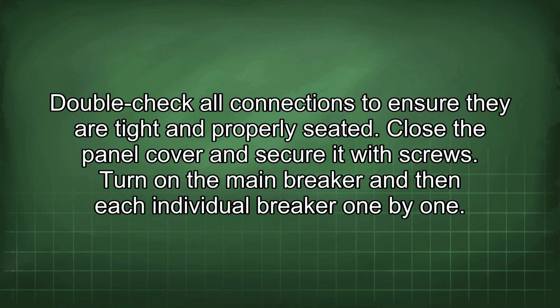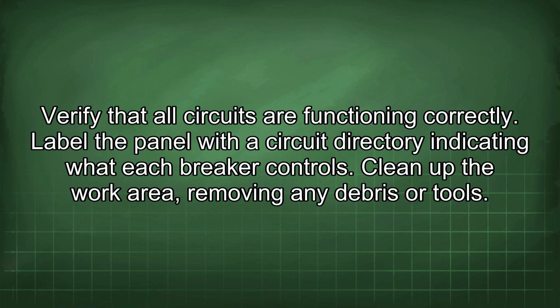Close the panel cover and secure it with screws. Turn on the main breaker and then each individual breaker one by one. Verify that all circuits are functioning correctly. Label the panel with a circuit directory indicating what each breaker controls. Clean up the work area, removing any debris or tools.